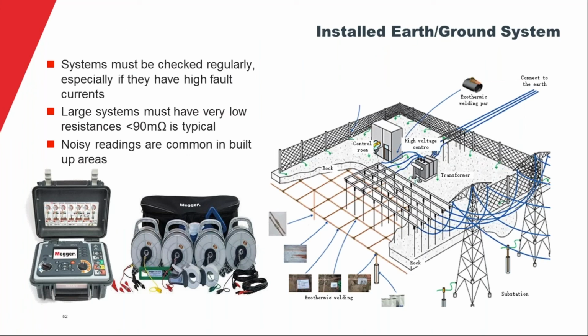And the last thing we're going to take a look at then, and this is just real quick, just the idea of substation testing is particularly demanding because of the noise problem. Worse than just about anywhere else. In our catalog that you see on the left there, the DET2/3 has enhanced noise suppression capabilities. It does continuous noise graphing, so you can see what the background was at the time that your measurement was actually posted. It has high and low test currents. You can adjust your test frequency to try to find the most quiet frequency, and it also has filtering. So just keep that in mind. If you're testing these types of environments, very, very noisy, you could either not get a measurement at all, or you could possibly walk away with an incorrect one. So make sure you get a high noise capability tester.